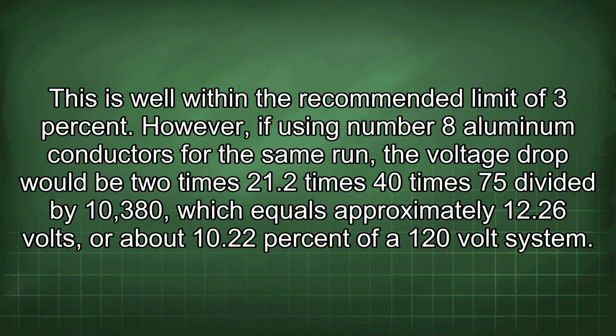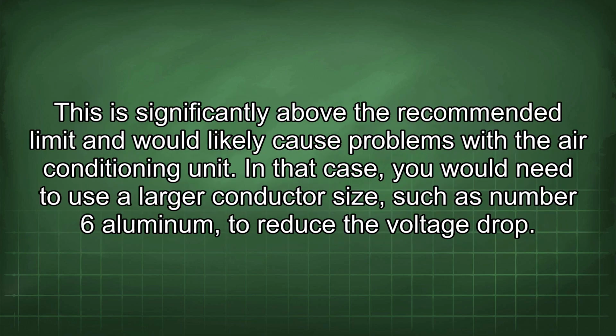However, if using number 8 aluminum conductors for the same run, the voltage drop would be 2 times 21.2 times 40 times 75 divided by 10,380, which equals approximately 12.26 volts, or about 10.22% of a 120 volt system. This is significantly above the recommended limit and would likely cause problems with the air conditioning unit.